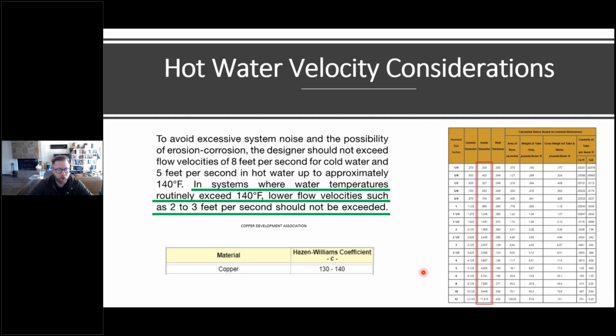So worth noting, though, just a quick note on velocity: when we're looking at velocity, definitely take a look at pipe materials and recognize the pipe material limits, both on temperature and velocity and other things. When you look at copper, the Copper Development Association indicates that for systems where water temperatures are below 140 degrees Fahrenheit, we can use up to 5 feet per second in a hot water for a continuous flow.